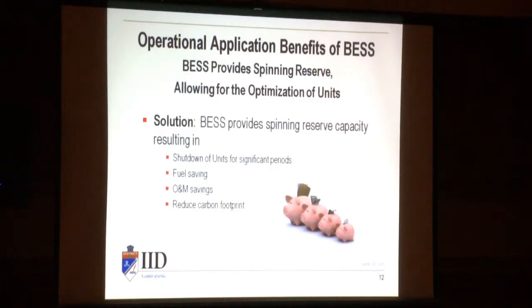The battery provides spinning reserve capacity, resulting in shutting down units for significant periods of time. The big thing for us, especially on our load profile, is that in summertime that's when our peak load is — we'll have all our units online and the solar online, so it's not as hard. However, in winter, when we drop down to almost 30% of our peak load and suddenly have numerous amounts of solar on, we have an opportunity to shut down our units, and the battery will be able to sit there and either absorb or put out power.